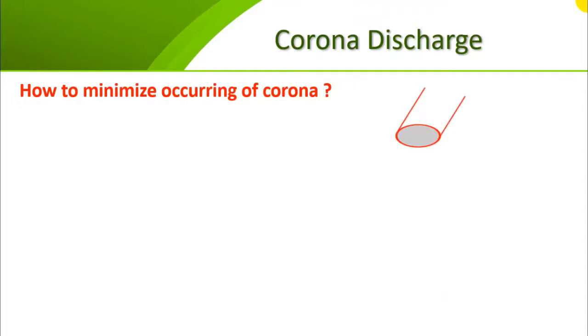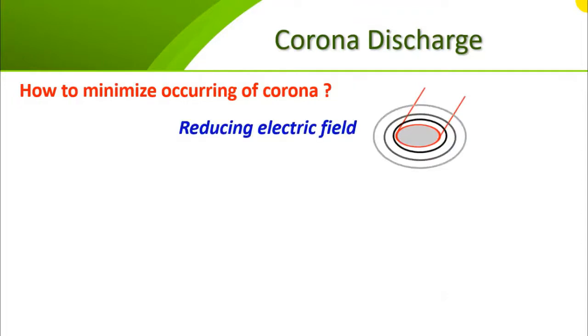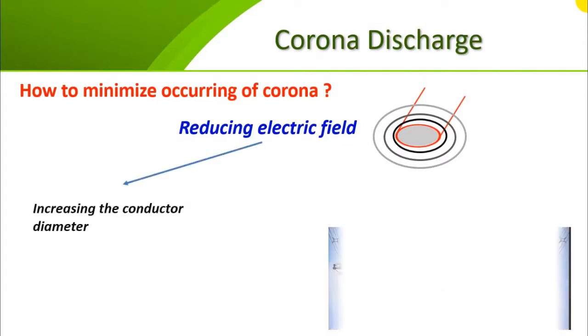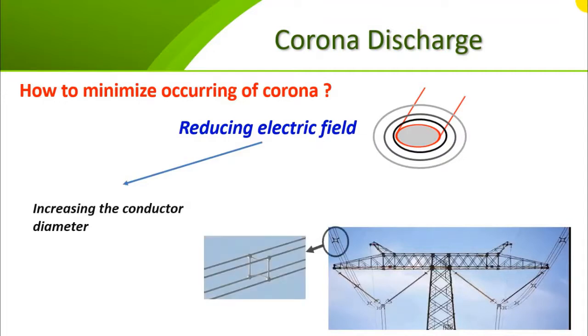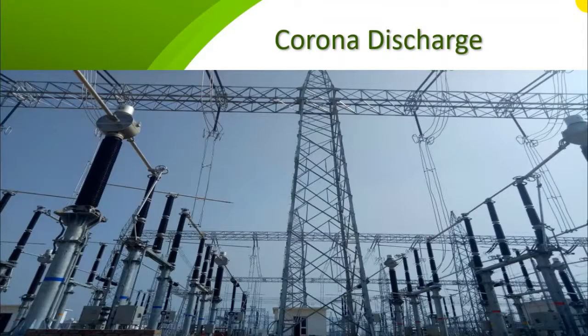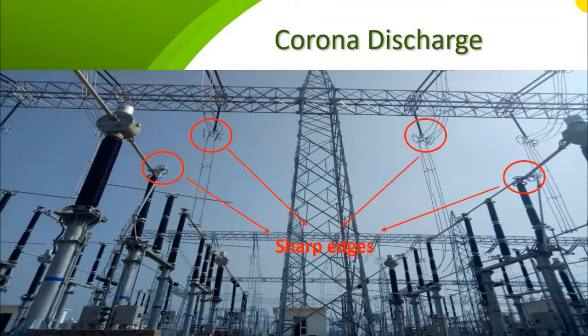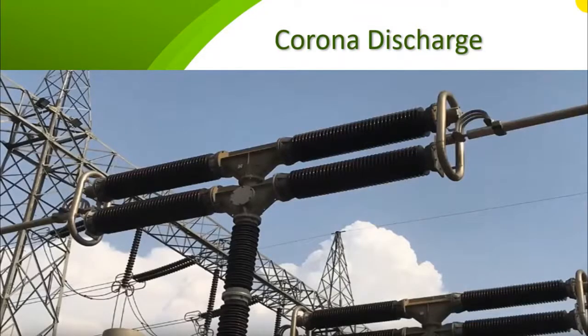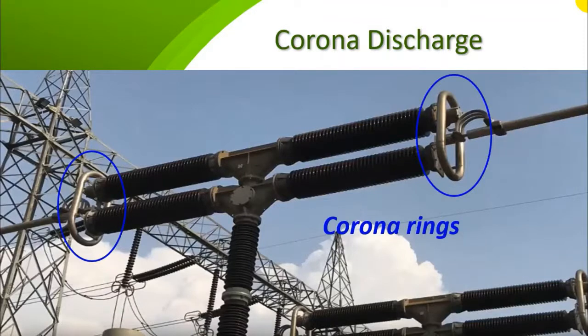To reduce corona, we should reduce the electric field produced by the conductor. This is done by either increasing the diameter of the conductor or arranging the conductors in sets of 2, 3 or 4 conductors per phase. This operation is called bundling of the conductor. Also, you should know that corona more possibly occurs at points having sharp edges or small curvatures, since the electric field is higher at such points. So to avoid this, we use corona rings. Corona rings are nothing but a ring made of thick conducting material. Corona rings actually reduce the electric field by giving a suitable and smooth curvature at sharp points. Therefore, the discharge current will not ionize the air, but it flows through the corona ring.